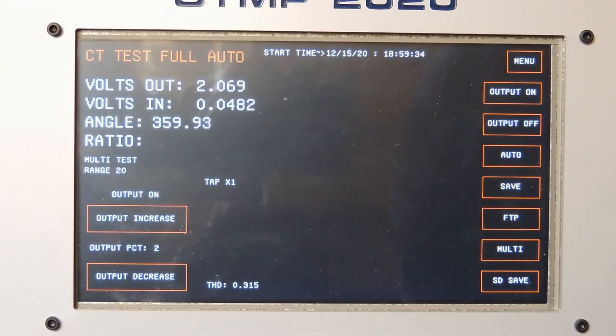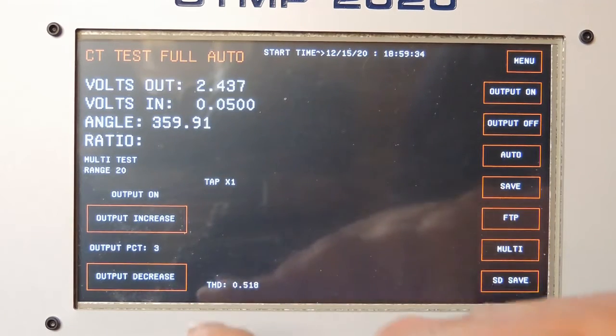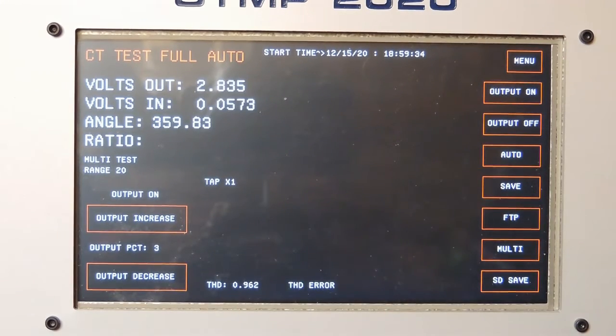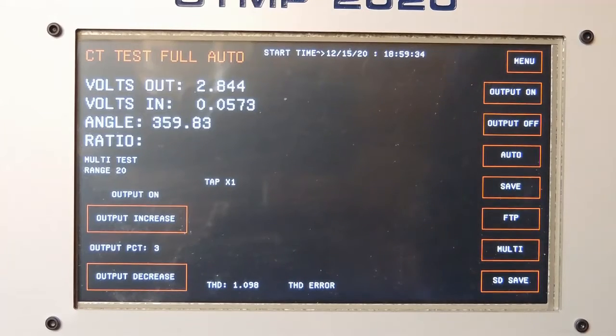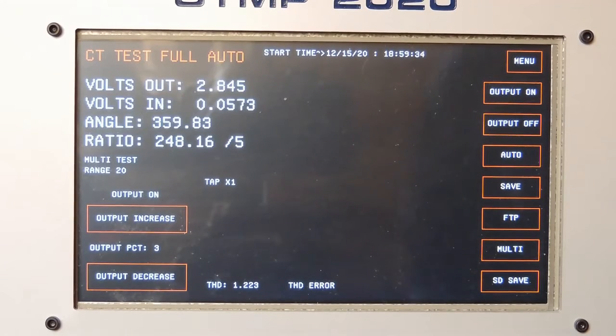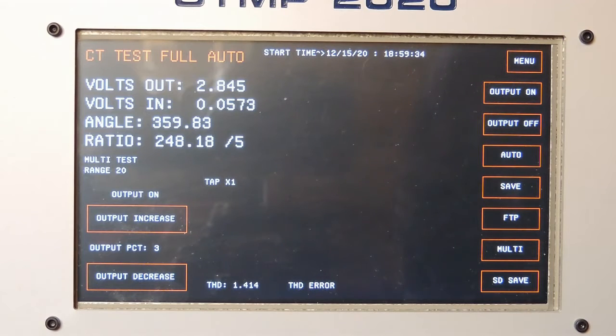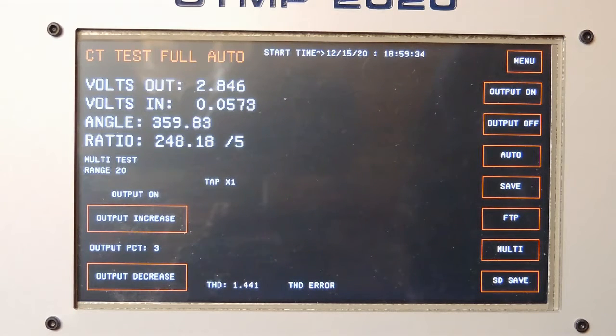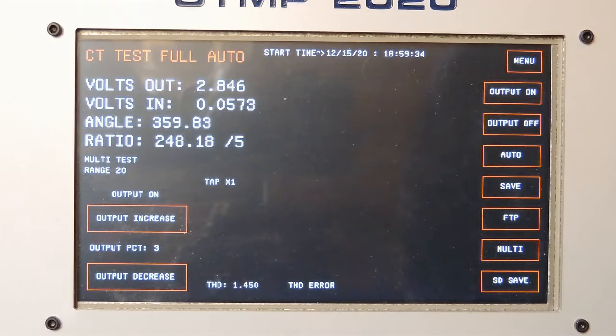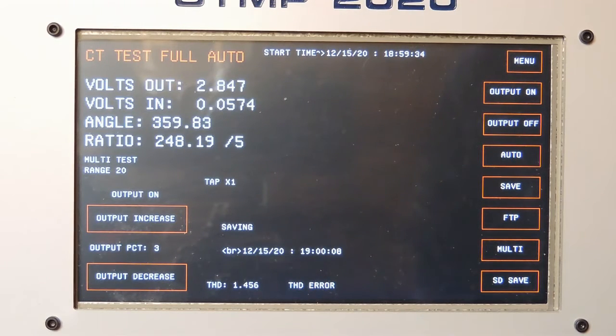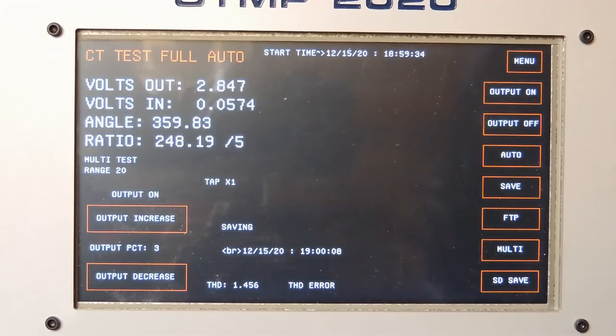The test set now prints the total harmonic distortion down here. It says THD error. That is caused by either saturation or remnants. So it won't go any further. It will just display a stop there and save that, the result at the lower level of excitation as the ratio result.